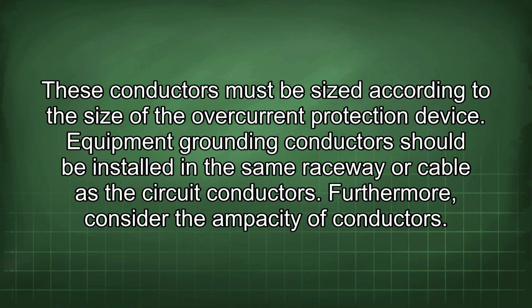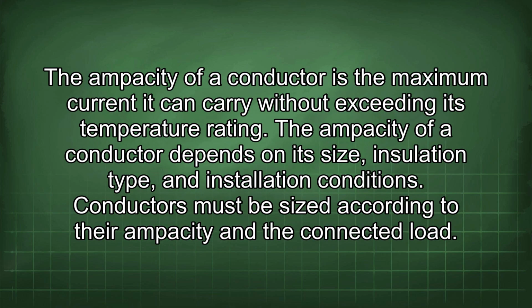Furthermore, consider the ampacity of conductors. The ampacity of a conductor is the maximum current it can carry without exceeding its temperature rating. The ampacity of a conductor depends on its size, insulation type, and installation conditions. Conductors must be sized according to their ampacity and the connected load.